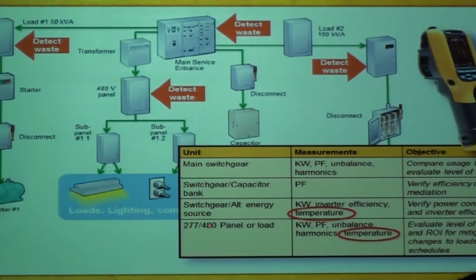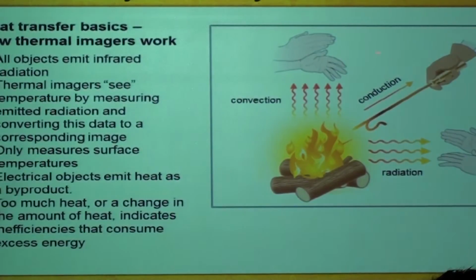In the 277, 480 panels and loads, again, temperature rise because of harmonics. If you know harmonics, harmonics is manifested as heat. It's extra current, right? It's added energy, and it's heat. So if you look at thermal imaging, why is it so important? And let's talk about heat waves by electrical systems.